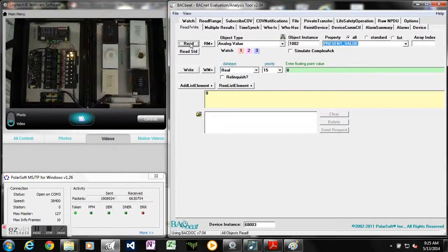So if we manually override multiple ones, there's 1 override relay number 3, then it shows 3 as the last overridden relay. Do another one, and it shows 8. Now 8 is the last overridden relay, and it will remain an 8 until those have been cleared out. So if I press and hold the clear button until it clears them out, then this value goes back to 0. And so that just allows you to monitor if any of your relays have been manually overridden.